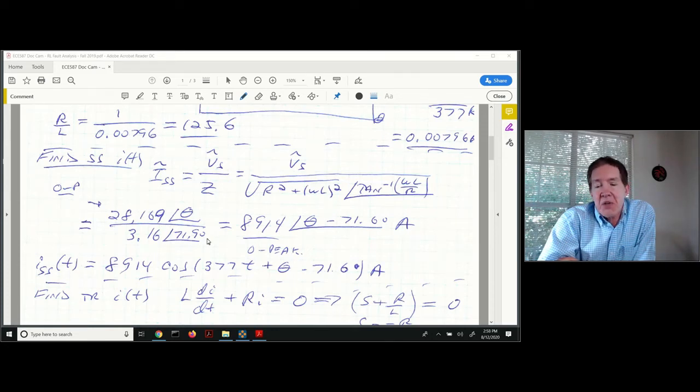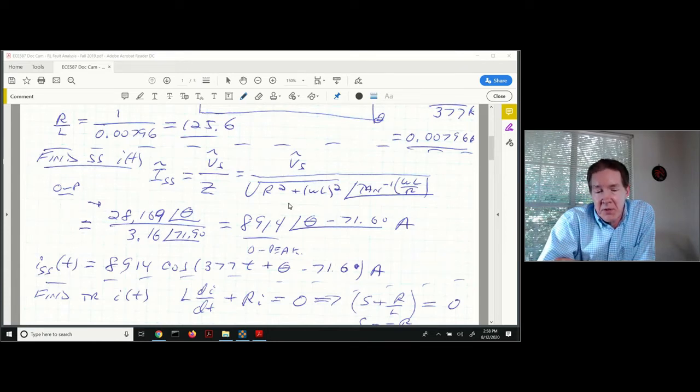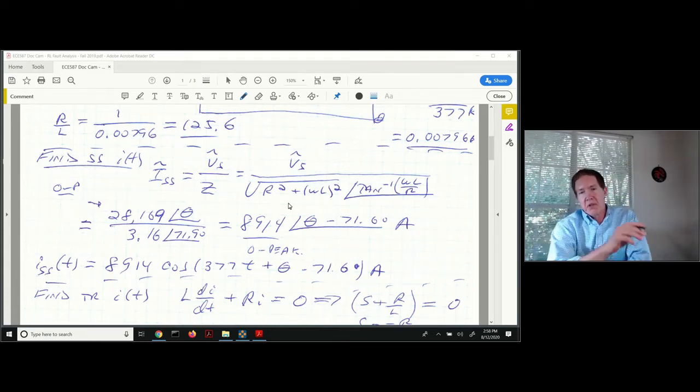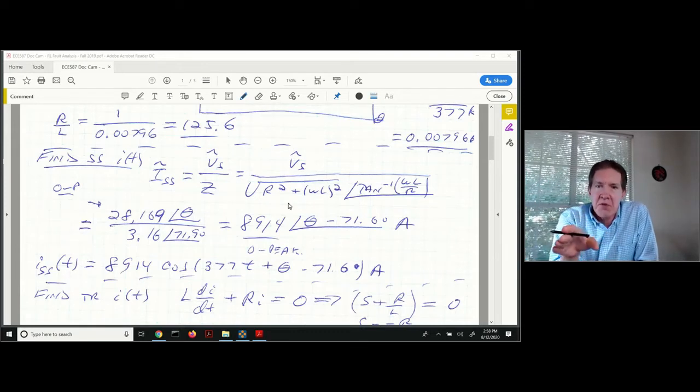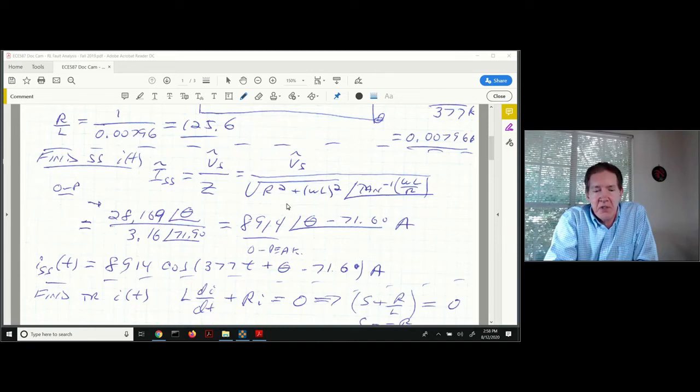The angle on the numerator corresponds with the point-of-wave angle of theta. I've got the angle of arctangent of omega L over R in the denominator. This gives me a steady state current with a zero to peak value of 8,914 at angle theta minus 71.6 degrees. In those waveforms I showed you before, this is what we would have in steady state.